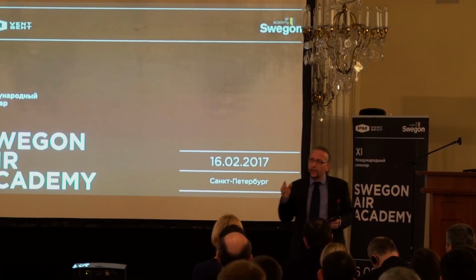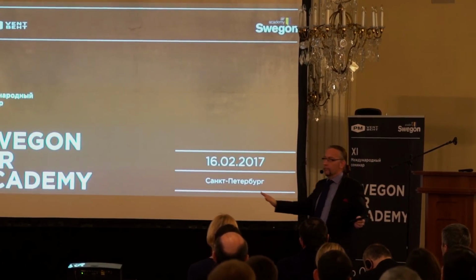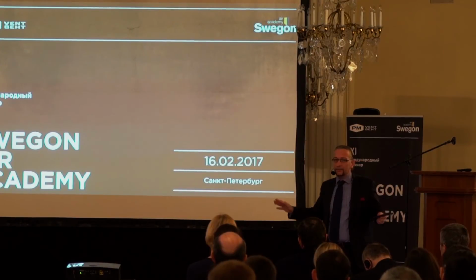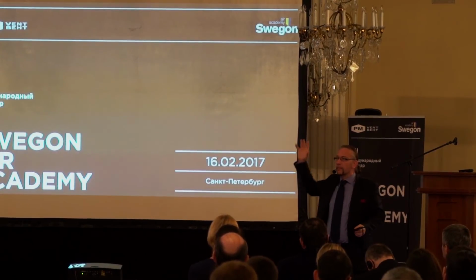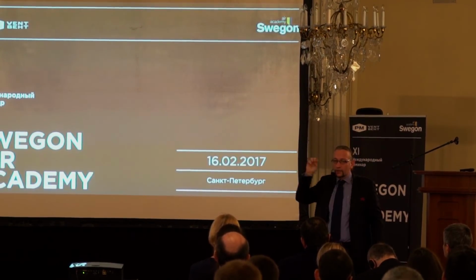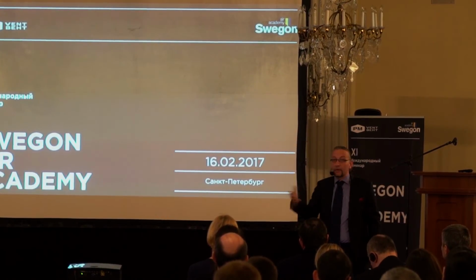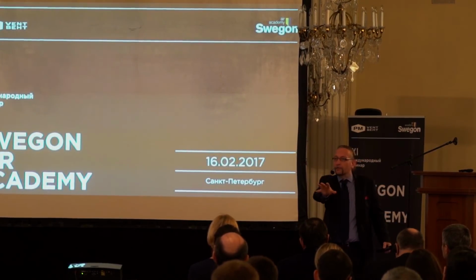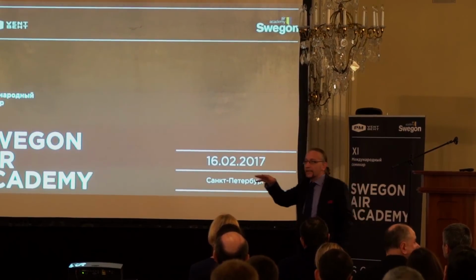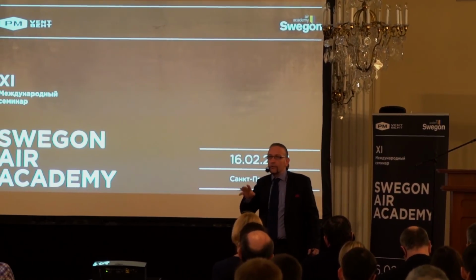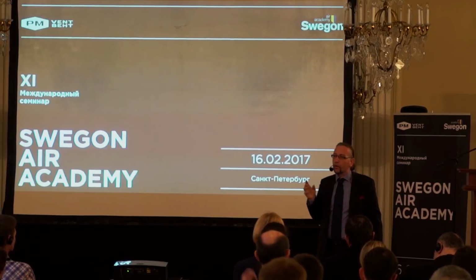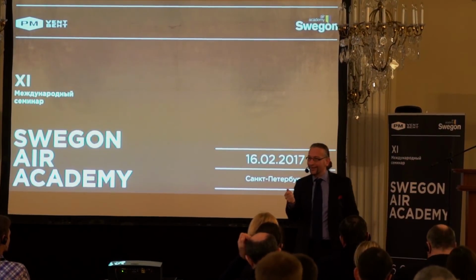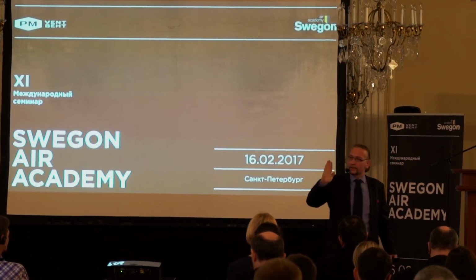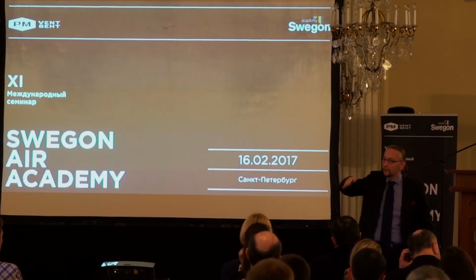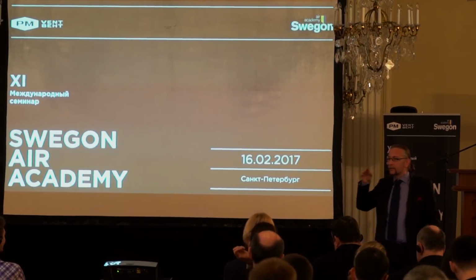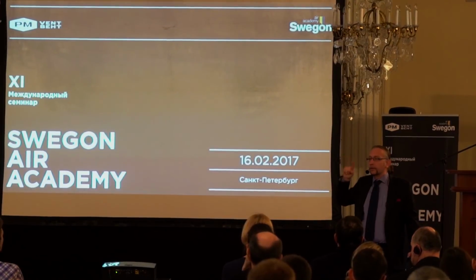So what you do is, if you imagine this room has to have enough capacity for all of you in here in the middle of summer. So this room needs a lot of air and a lot of cooling power. Well, now it's not in the middle of summer, but there are a lot of people in here, but you already need less cooling power. So this room in 99% of the year will not operate on full power, okay? Which means normally that the dampers would be closing, the valves would be closing. And that is true for the different rooms in this building.